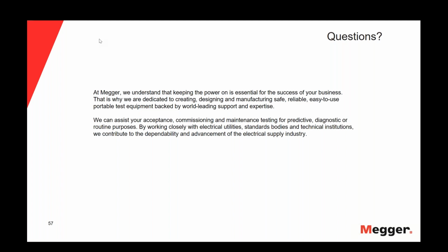Okay, lots of IEC questions here. So the way this all originated was VLF came up in the 1980s because then these issues with the DC testing on the solid dielectric cables came up. A certain company patented this technology, and it became widespread in the industry, pretty much became a quasi-standard, and then it became a standard.